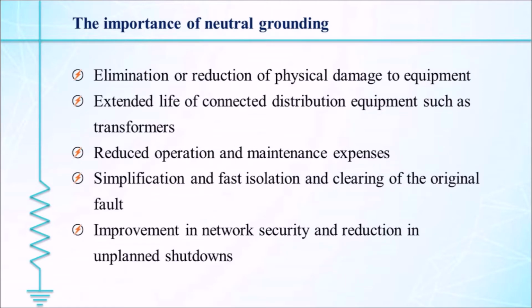Hello everyone, my name is Vaibhav Surve. Now I will explain the importance of neutral grounding. As we know, if we have to drive any system, we have to maintain the balance. We have to maintain the proper balance between the system and system coordination. Same as in a 3-phase electrical system, where maintaining balance is the most essential. During unbalanced conditions at the distribution side, all unbalanced current is grounded through the neutral. Hence, if we ground the neutral properly, the balance can be kept proper as well as the continuous supply can be maintained. These are some important points which tell us why we need to ground the neutral.